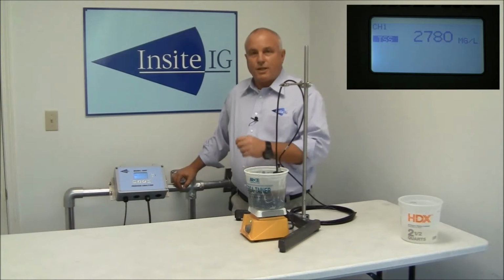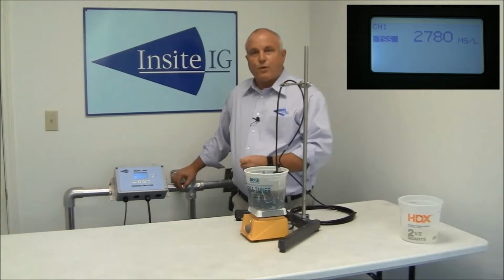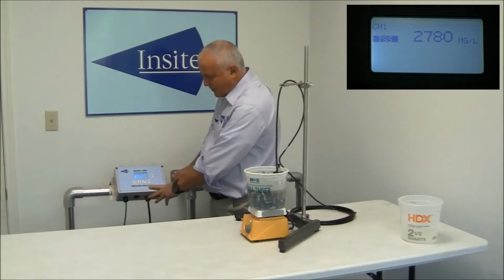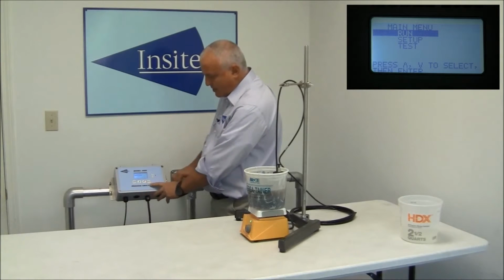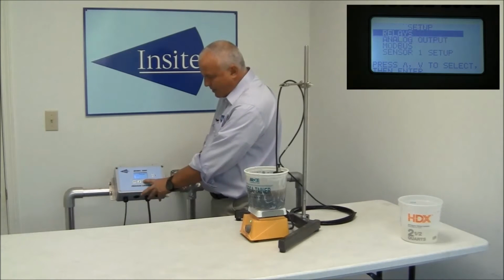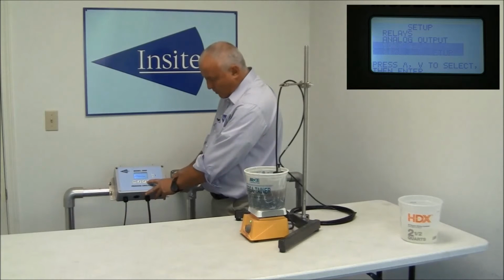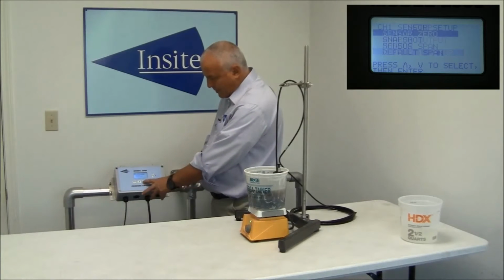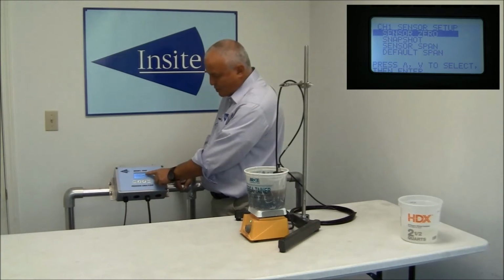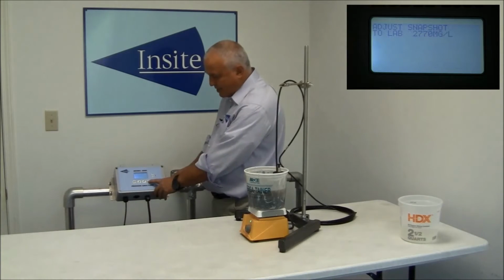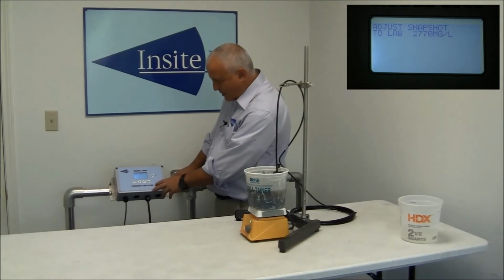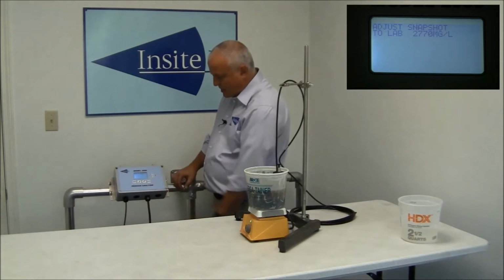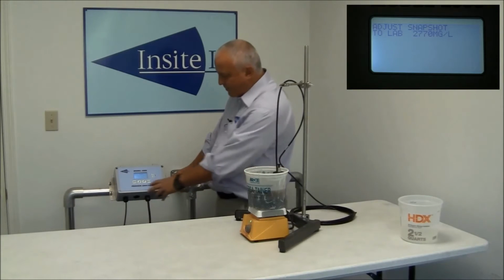At this point, you would send off your lab, and then when you get the lab result back, be it the next day or whatever, you would come back to the instrument, press menu, go down to setup, press enter. Again, down to setup sensor. At this time, you would do sensor span, press enter. It comes up with the number that it thought it was last time, 2780.